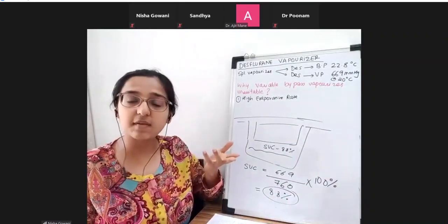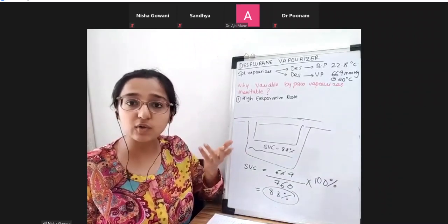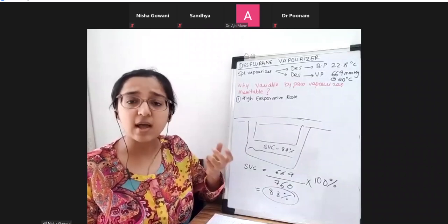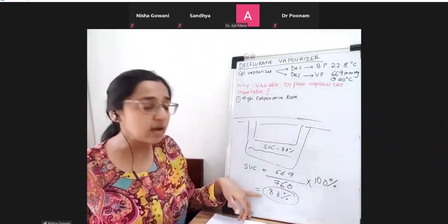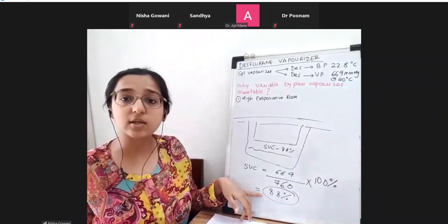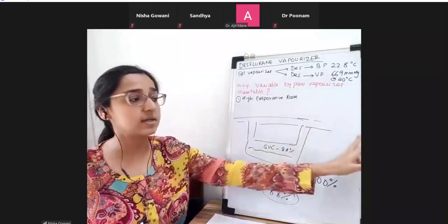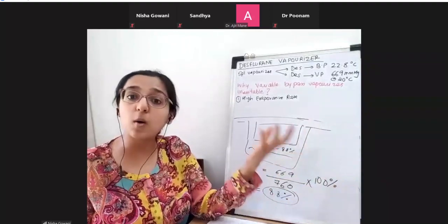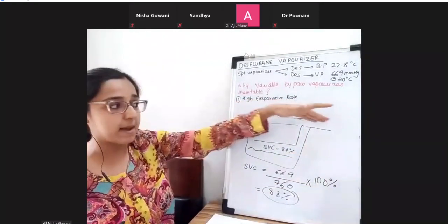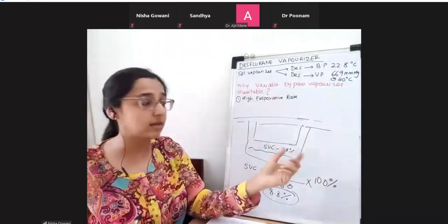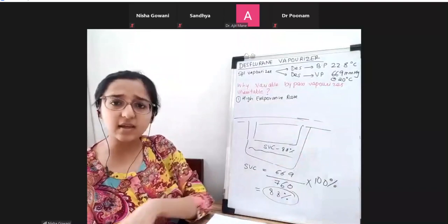How much desflurane do we want to deliver to the patient? We want to give only 6%, right? That is a clinical value at which desflurane is used. 5%, 6%. So I want to dilute 88% to 6%. Although 88 is here, I want 6 to go out. So can you imagine how much fresh gas flow I will need from the bypass chamber to dilute the 88 to make it 6%, right? So that is not feasible. So that is one of the reasons that we need a specialized vaporizer.